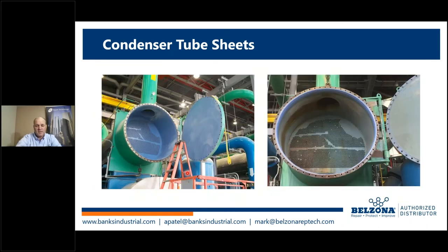So this is a neat one. This is actually at a big university in Pennsylvania that has lots and lots of these. This is a very large heat exchanger, actually only goes through one side, but this is when we coated it back in 2005. And here we have it opened up back here in 2018. It's dirty, but the coating is still intact. It's still doing its job. They open this every single year and check it. As you see, they have lost some tubes. The tubes start to degrade just on their own, but those plugs are where the tubes have been plugged.